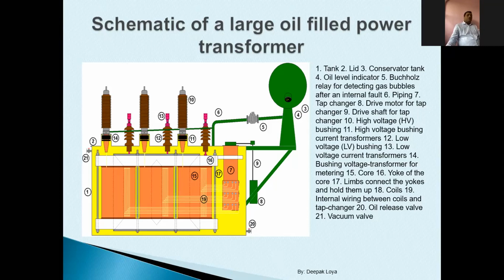And the common protections which are fitted on the transformer itself, apart from the electrical relays which are kept outside of the transformer or in my control room. So which are these protections? Basically, these are: Buchholz relay, pressure relief device, winding temperature monitor, oil temperature monitor, oil level gauge. So these are all protection equipment. So there is a Buchholz relay.